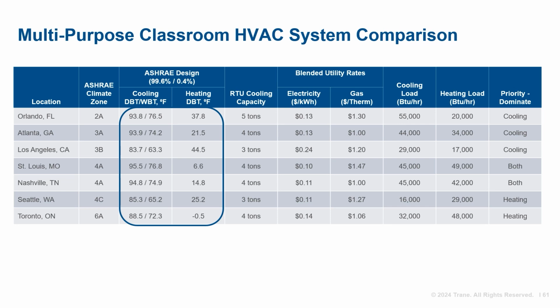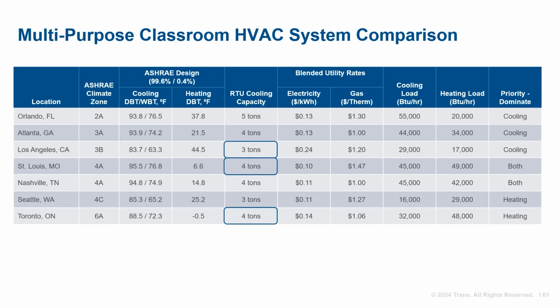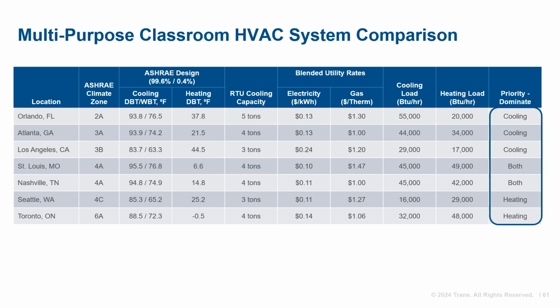The size of the rooftop unit and cooling capacity varied from 3 tons in Los Angeles, California, to 4 tons in St. Louis and Toronto, Ontario, while a 5-ton unit is required in Orlando, Florida, to meet space design conditions. From the load calculations, we were able to determine if the location is cooling or heating dominant or both, where the heat gain and heat loss are relatively equal. The unit in our example is sized to handle the cooling load.